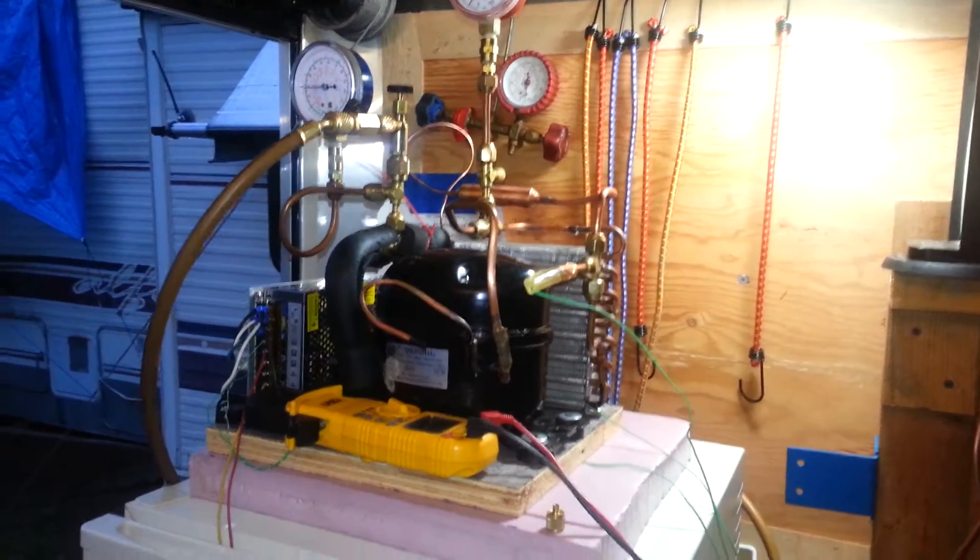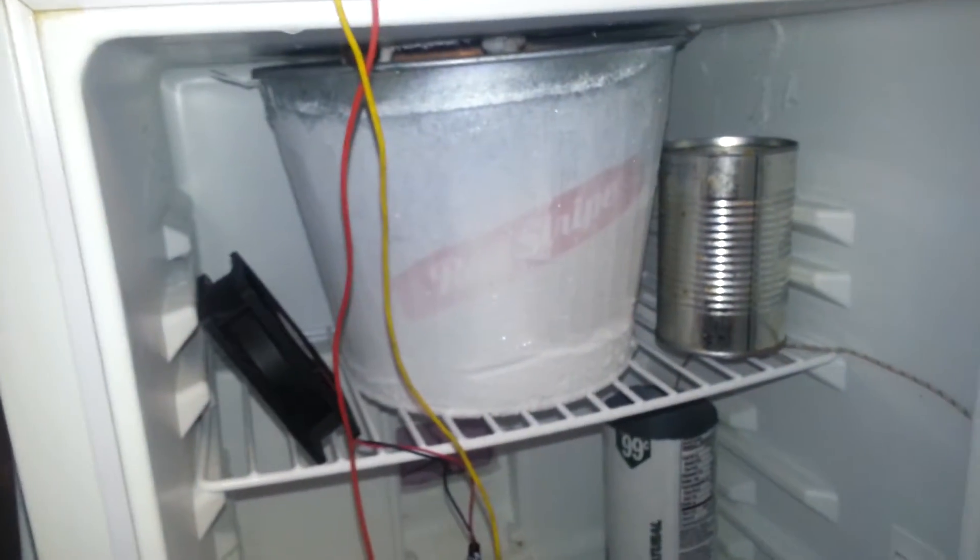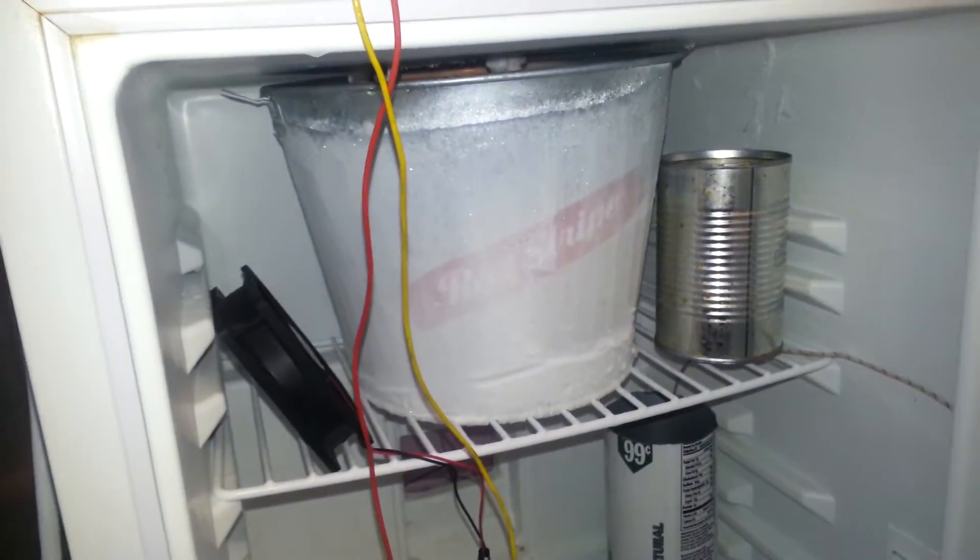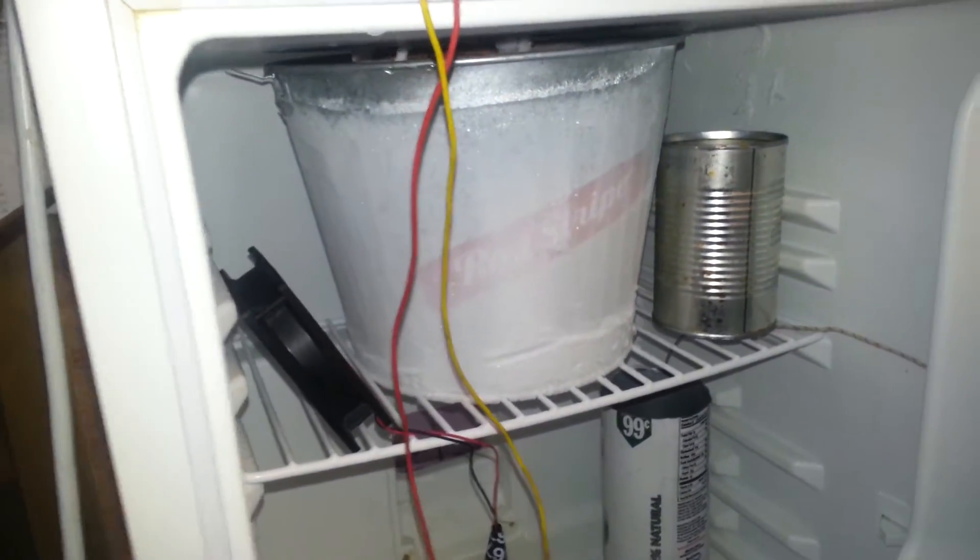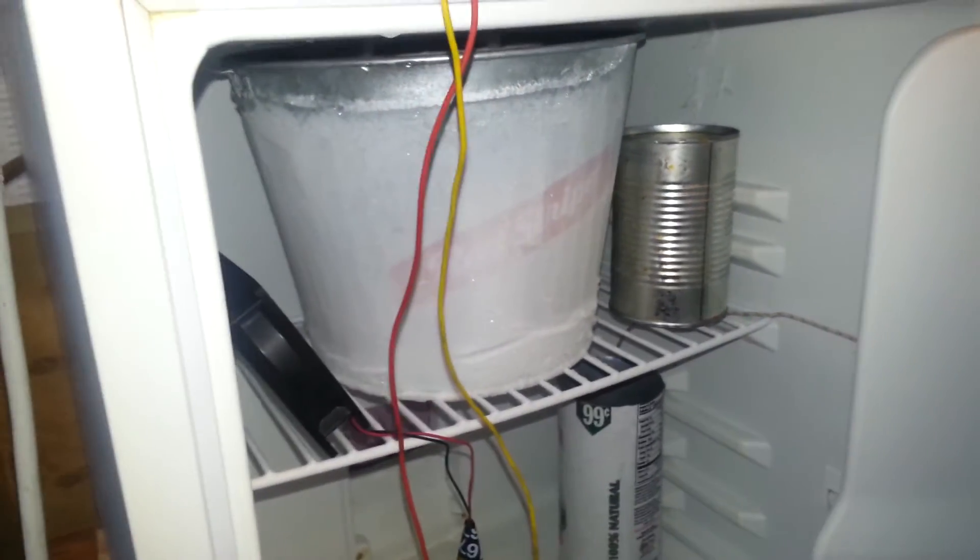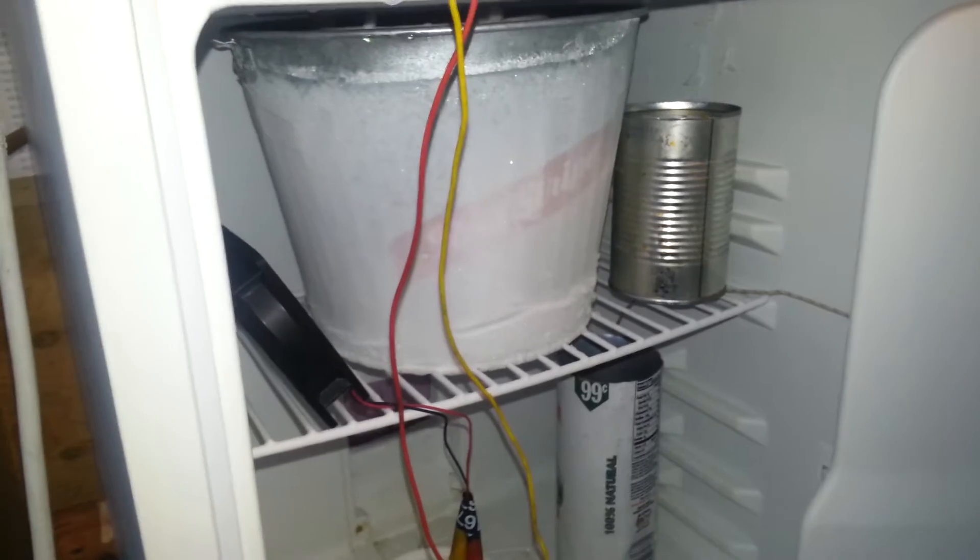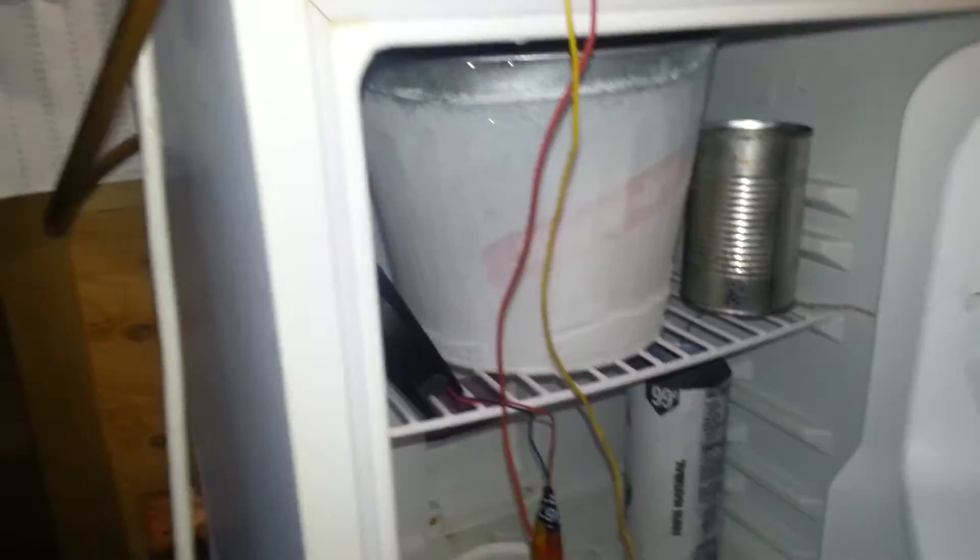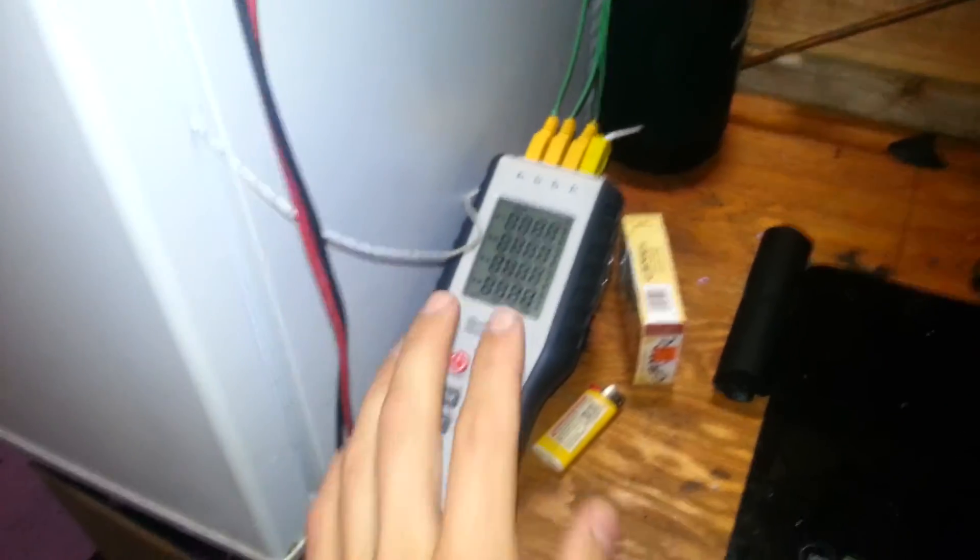I did so maintaining the glycol bucket that is inside this box right there. Propylene glycol in there with water, maintain that between zero and ten degrees Fahrenheit. Once it would reach zero degrees Fahrenheit, I'd shut the compressor off with the circulating fan inside run and observe the temperature drop inside.